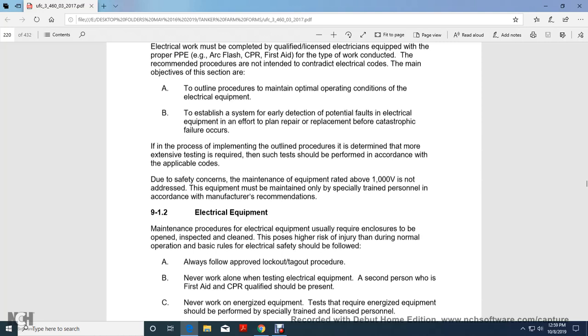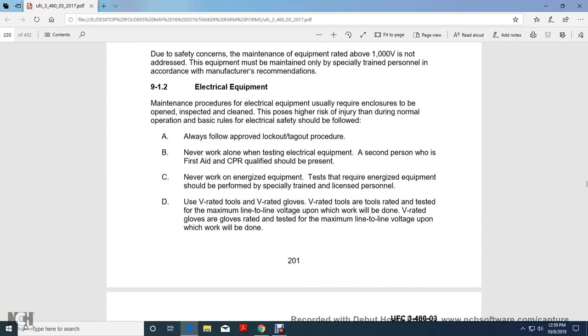If, in the process of implementing the outlined procedures, it is determined that more extensive testing is required, such tests should be performed in accordance with the applicable codes. Due to safety concerns, maintaining equipment rated above 1,000 volts is not addressed. That equipment must be maintained only by specially trained personnel in accordance with the manufacturer's recommendations. With electrical equipment, the maintenance procedure usually requires opening the enclosure, inspecting, and cleaning, which carries a higher risk of injury than normal operation.